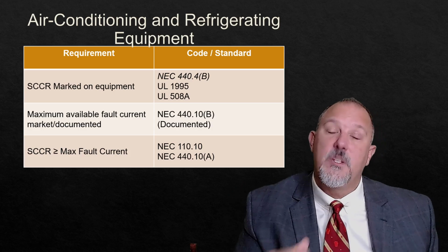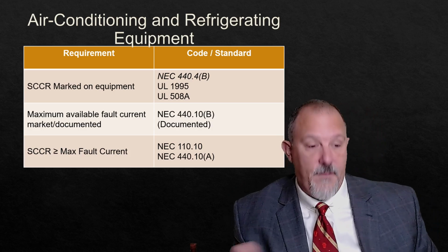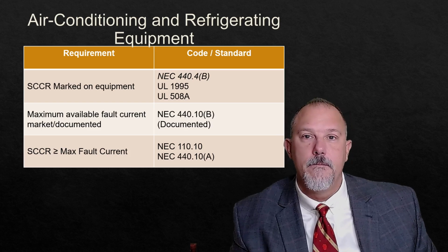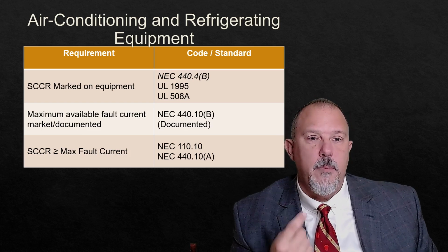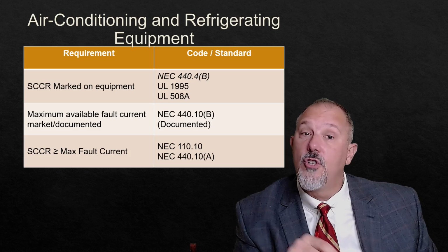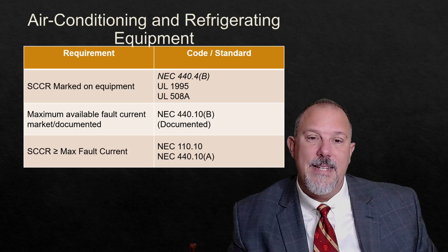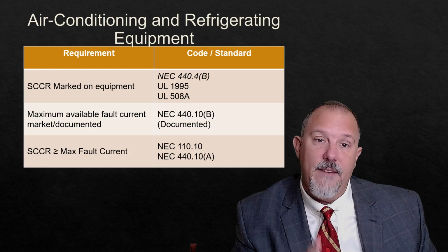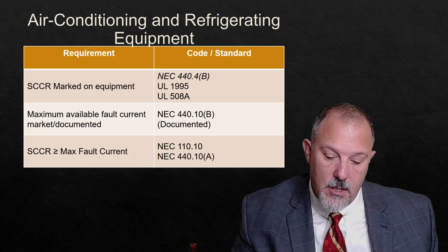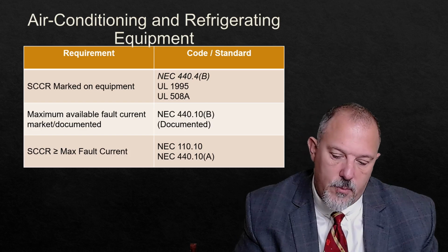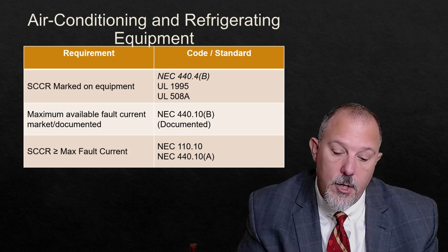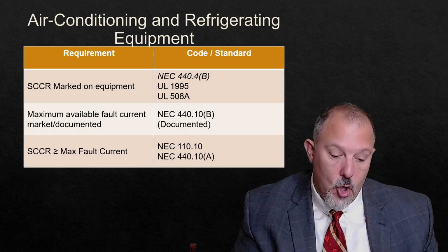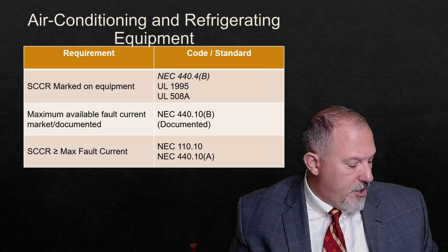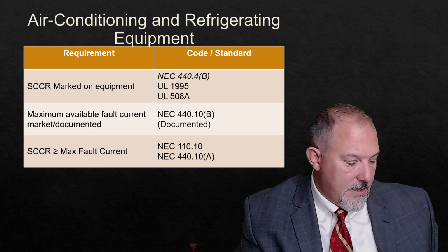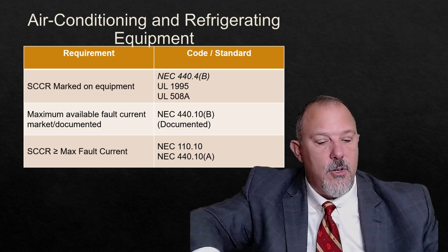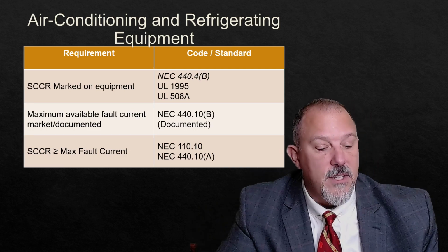So this is why many inspectors will simply look for the listing. If it's listed, that data has got to be there. The maximum available fault current has to be marked or documented as per 440.10B and available to the authority having jurisdiction. Let's just take a look at 440. Since we're here, let's read 440.10B. And I know that you have all opened your book to page 336. 440.10 is titled Short Circuit Current Rating, and B is Documentation.